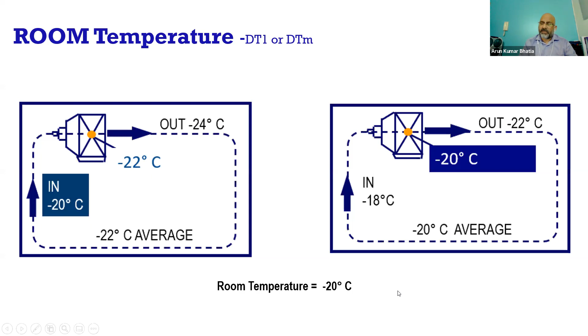Now, as an engineer, you have two kinds of evaporators. You can have fans on the front side of the evaporator, or fans behind the evaporator. What I'm trying to say is you can blow air through the coils, or draw air through the coil. I'm sure as refrigeration or HVAC engineers you must have heard of induced draft or forced draft principles of air - this is the same thing.